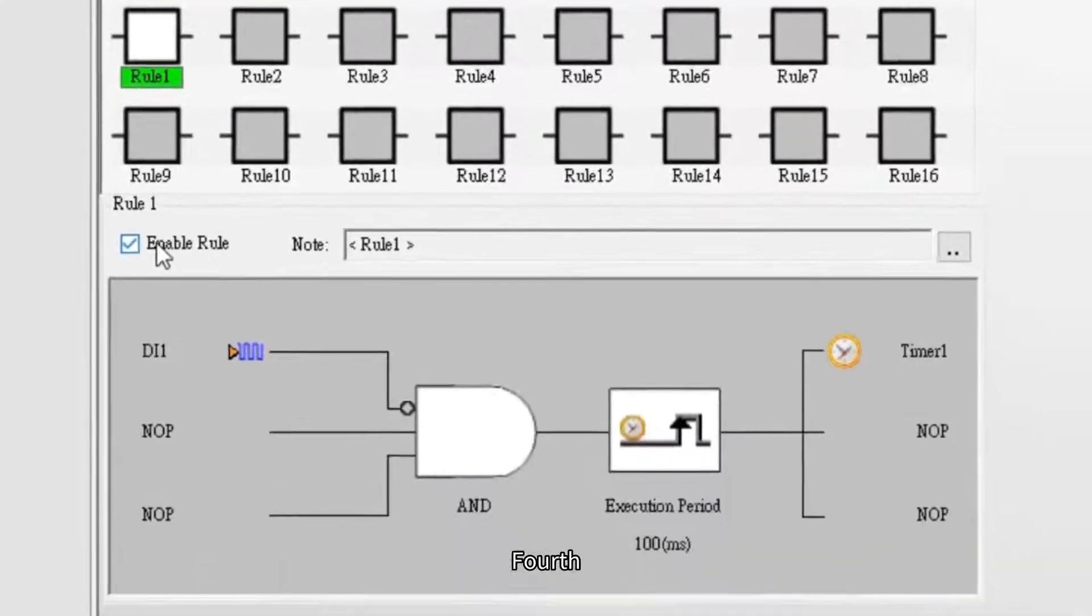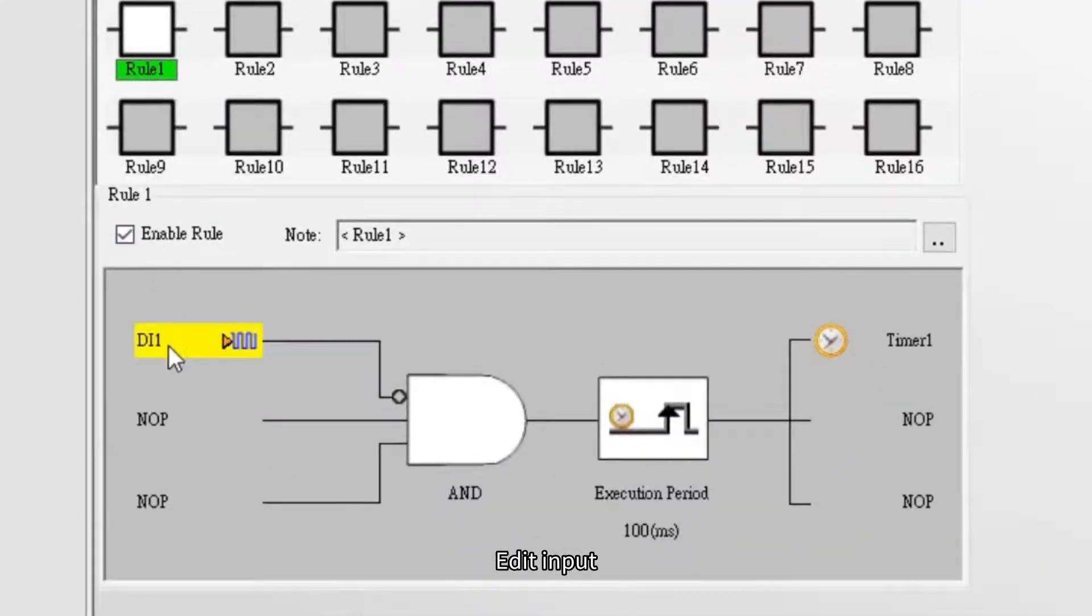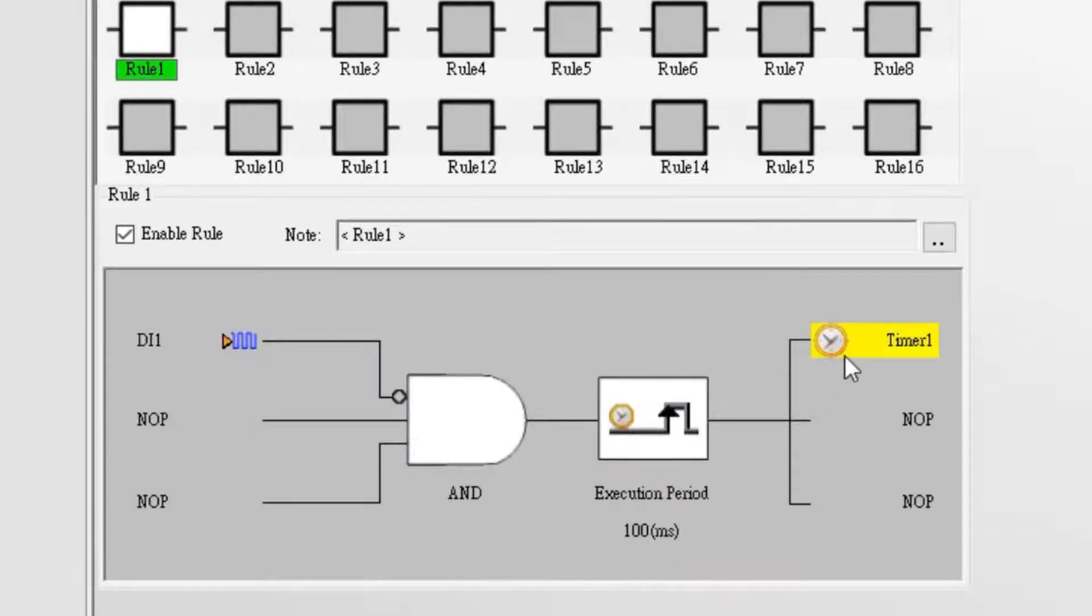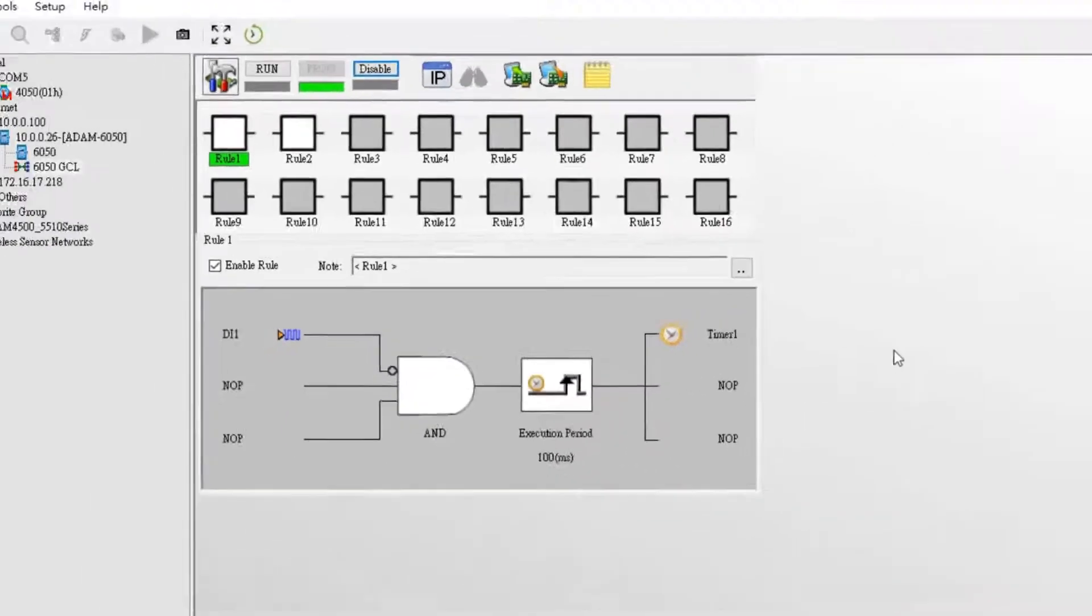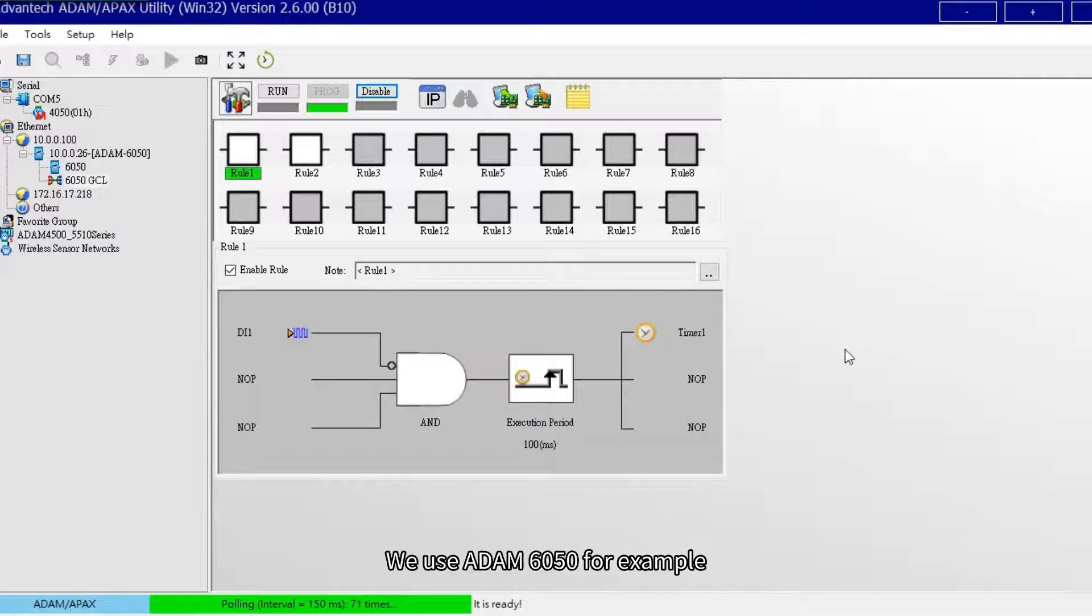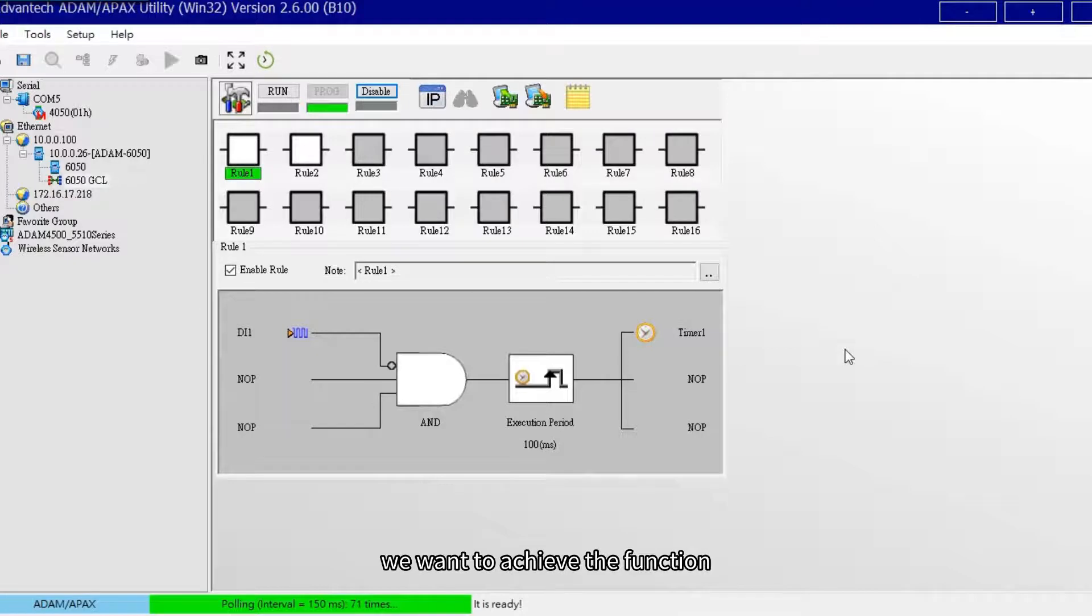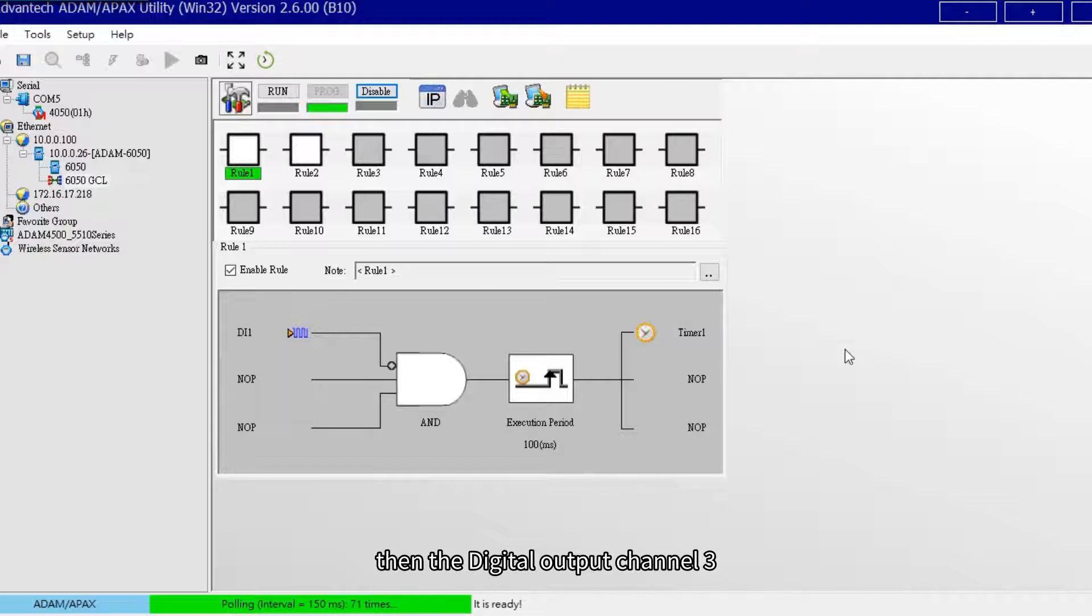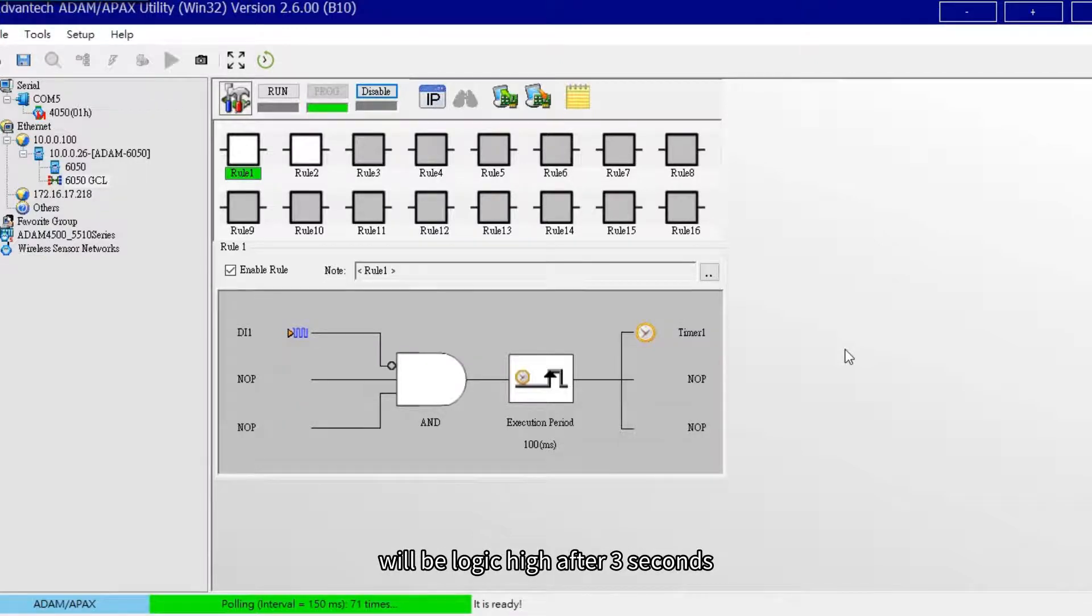Fourth, edit input, logic gate, execute, and output configuration stage. Now let's get started with the first example. We use ADAM 6050 for example. We want to achieve the function: when digital input channel 1 gets logic low, then the digital output channel 3 will get logic high after 3 seconds.